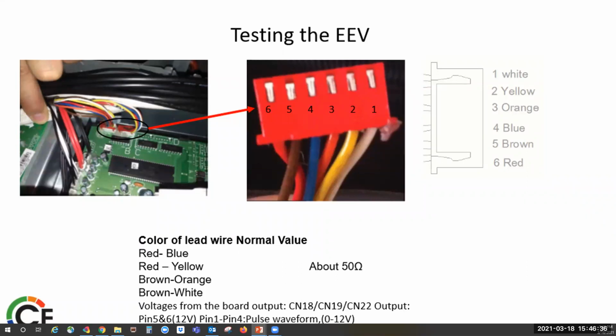But when you're checking your voltage, this is when you're really going to want to refer to your service manual because in this particular instance, CN18, CN19, and CN22 are your outputs. And you're looking for 12 volts DC on those. And it's going to be between pin 1 and 4. You're also going to have a waveform between 0 and 12 volts DC. And once again, you're going to need needle probes for this. I can't tell you how many times they say, well, my probes don't fit, and we have to go get some thermostat wire and make it work.